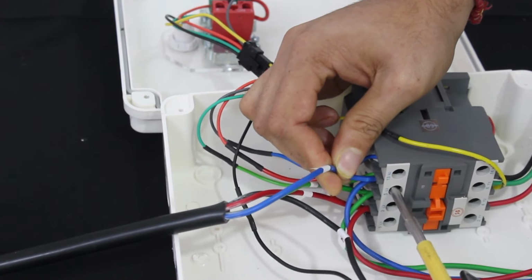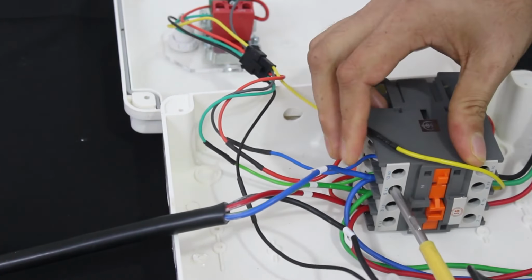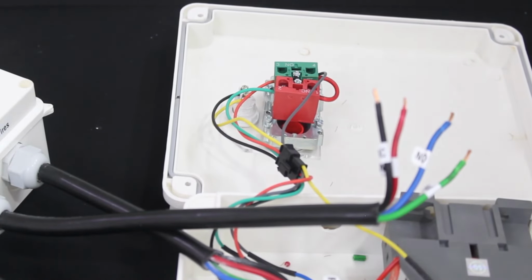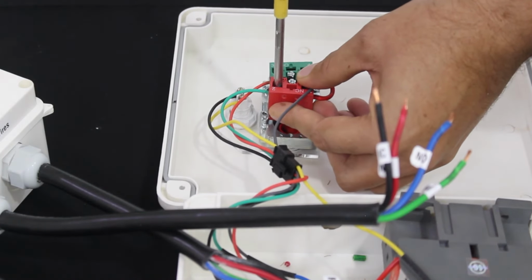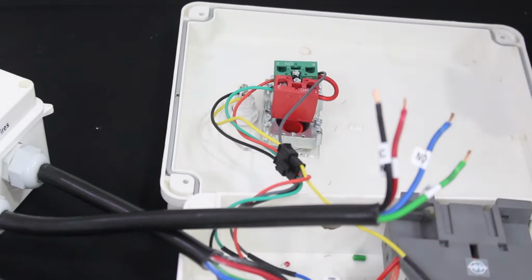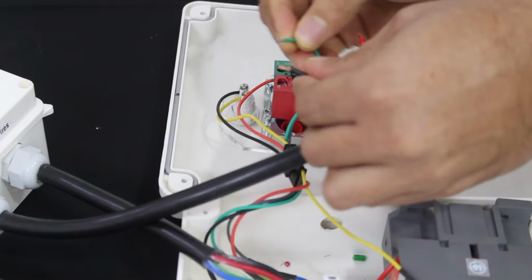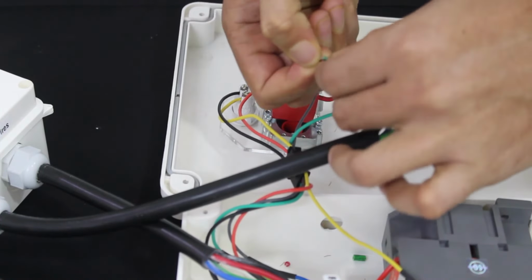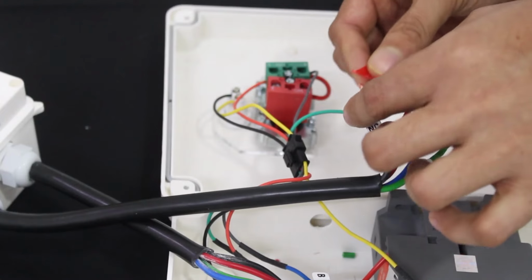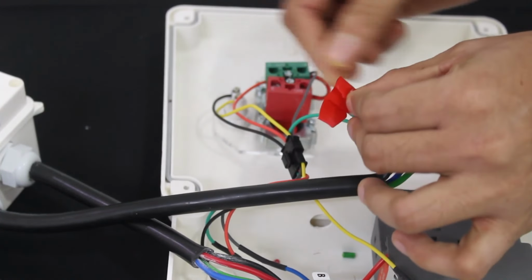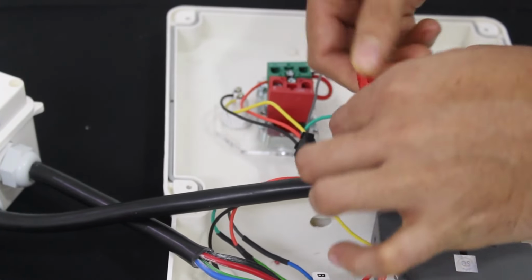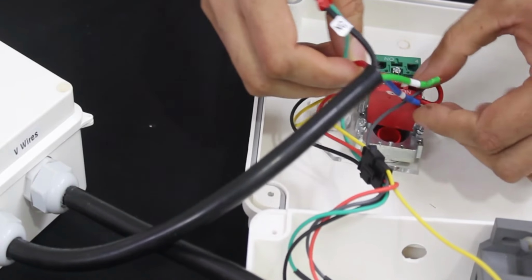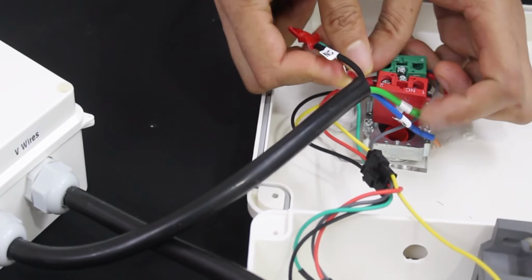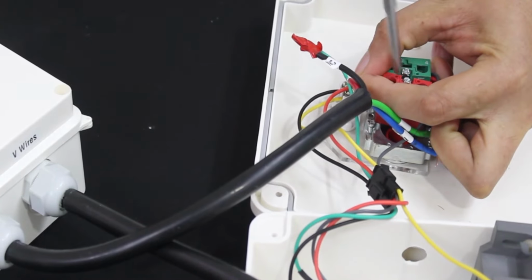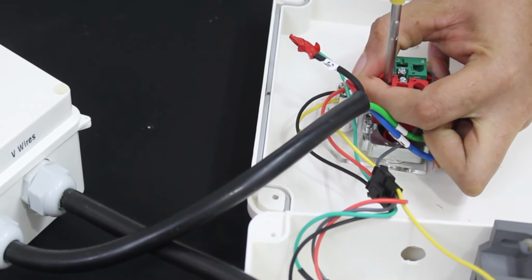Now that all the V wires are connected, let's join the NO-NC wires. Remove the wire from slot 2 on the NC terminal present in the contactor and connect it with the black NC wire present in the power module. Make sure to wrap the connection with an insulation tape. Take the red NC wire from the power module and connect it to the slot 2 on the NC terminal.